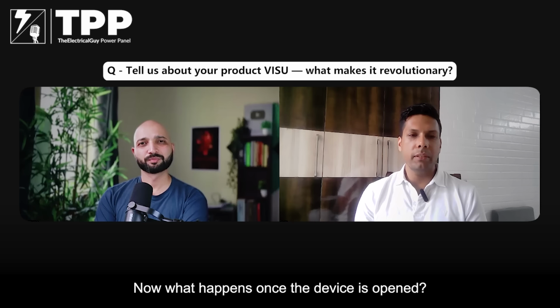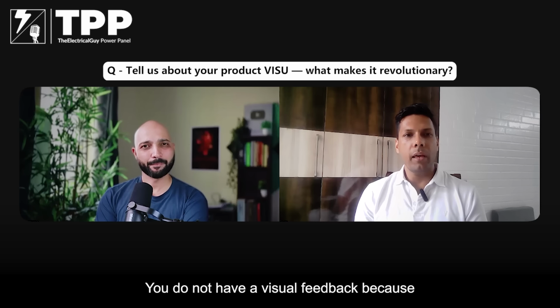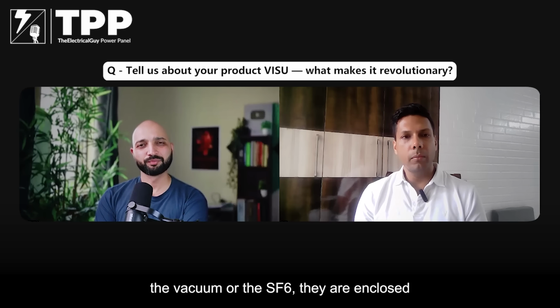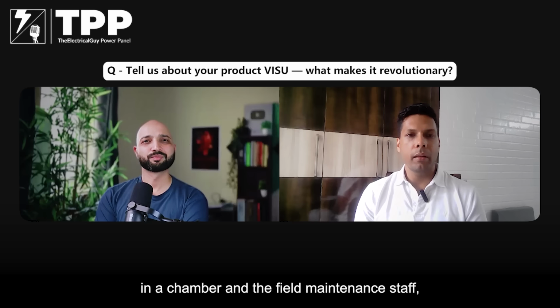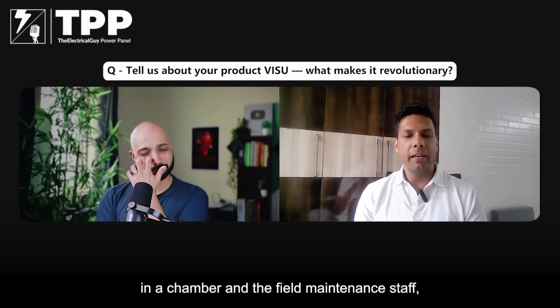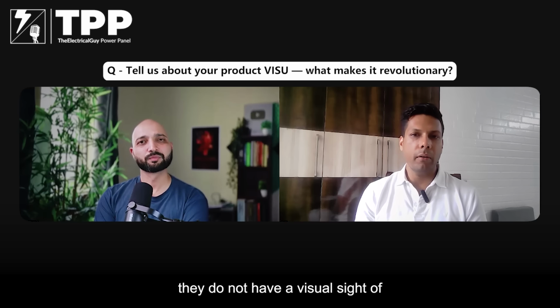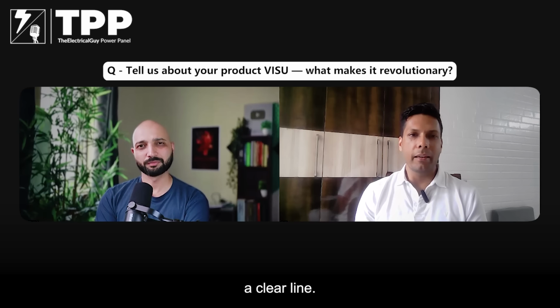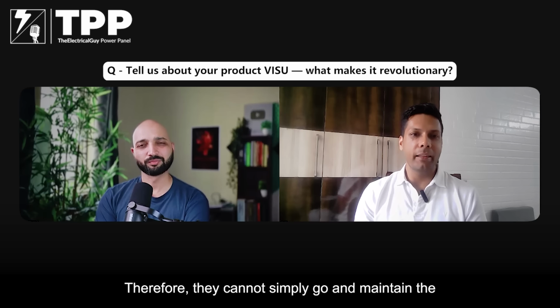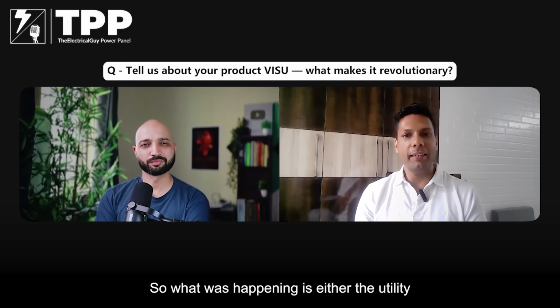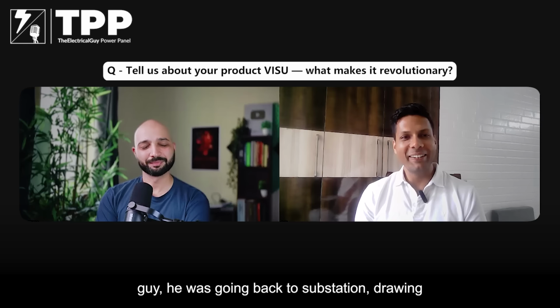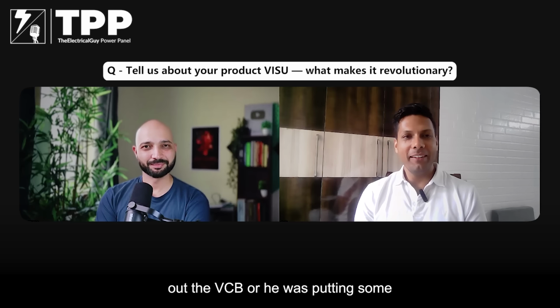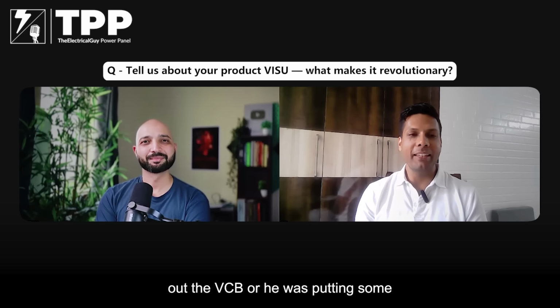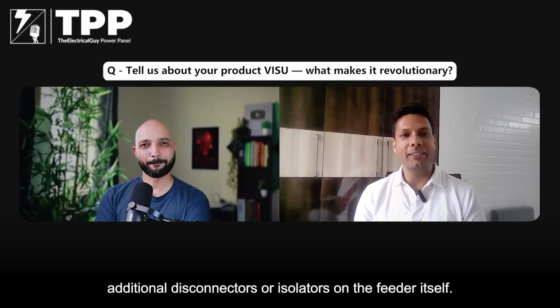Now, what happens once the device is opened? You do not have a visual feedback because the vacuum or the SF6 are enclosed in a chamber, and the field maintenance staff do not have a visual sight of a clear line. Therefore, they cannot simply go and maintain the line. So what was happening is either the utility guy was going back to the substation, drawing out the VCB, or he was putting some additional disconnectors or isolators on the feeder itself.